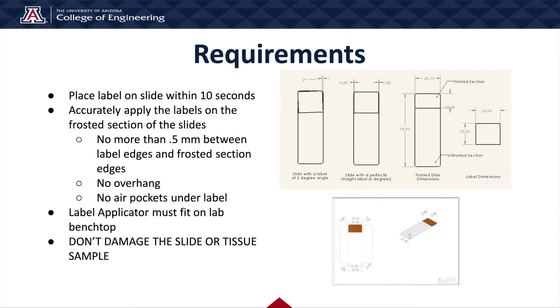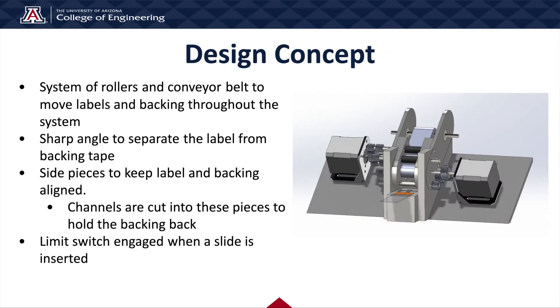Some of our main requirements for this project were to place the label on the slide within 10 seconds. We also needed to make sure the labels were placed accurately within the frosted section of the slide. This means the label edges could be no more than half a millimeter from the edges of the frosted section, with no overhang and no air pockets underneath the label. The applicator must also fit within the size requirements for a lab benchtop, and most importantly, not damage the slide or the tissue sample.